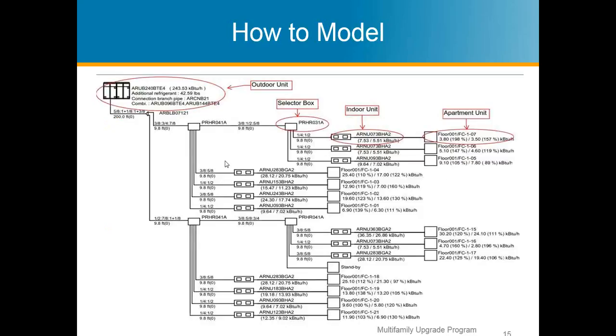Here's a line diagram of that same property, just to show you how they all talk to each other. So you have what's called a selector box when you're dealing with the heat recovery systems, and basically the selector box is the gatekeeper of who needs the refrigerant. So you have your outdoor unit, which is your main guy that's going to be there to help support any of the unmet loads that the indoor units can't share. If you can't get enough refrigerant or cooling capacity to cool that space through the heat pump and the heat recovery system, then your condensing unit takes over and helps out with that.